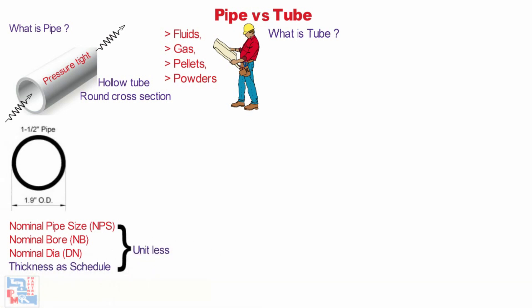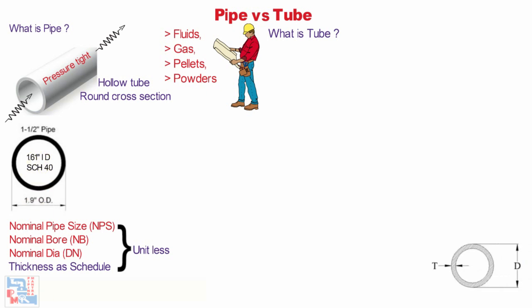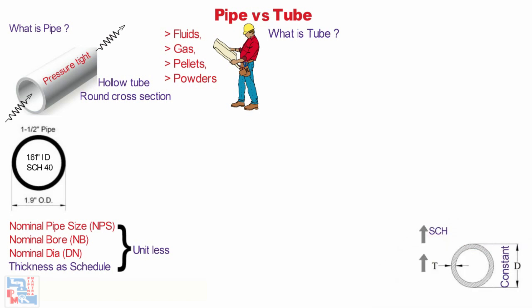Pipes are defined on the basis of unitless nominal pipe size (NPS), nominal bore (NB), nominal diameter (DN), and thickness as schedule. As you can see in this picture, NPS 1.5 inches pipe has an outer diameter fixed at 1.9 inches. The internal diameter changes based on thickness — for schedule 40, it is 1.61 inches. For a given NPS, the outside diameter stays constant and the wall thickness increases with a larger schedule number. The inside diameter depends upon the pipe wall thickness specified by the schedule number.